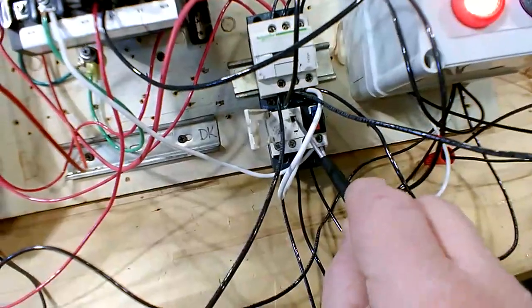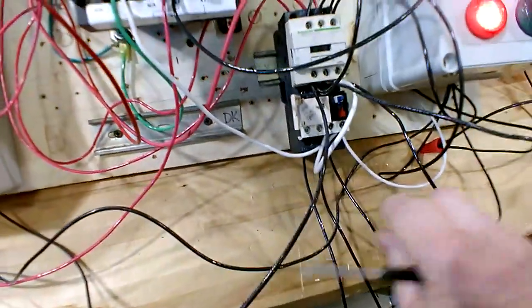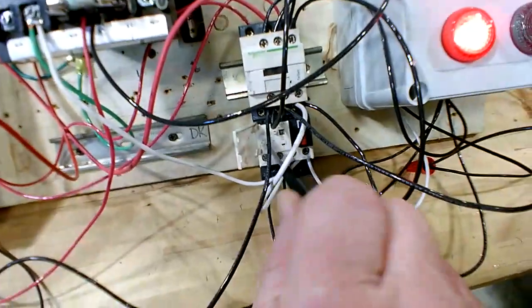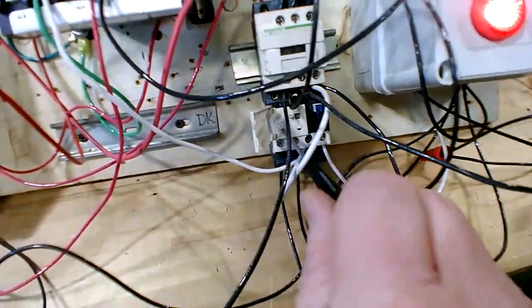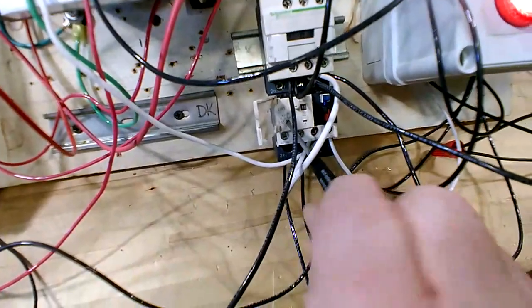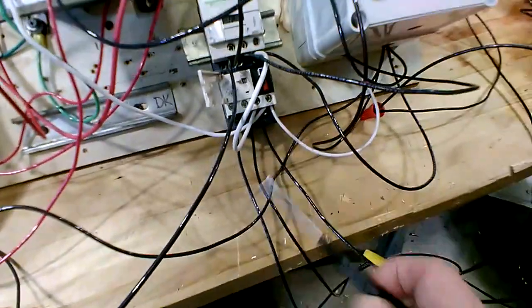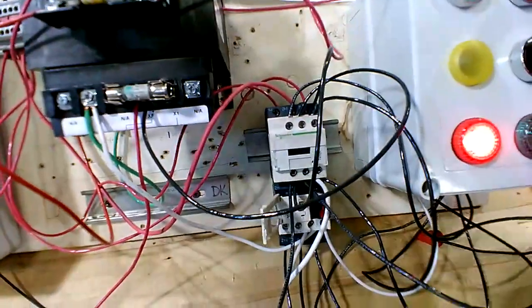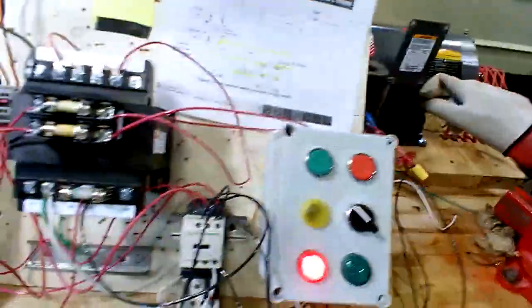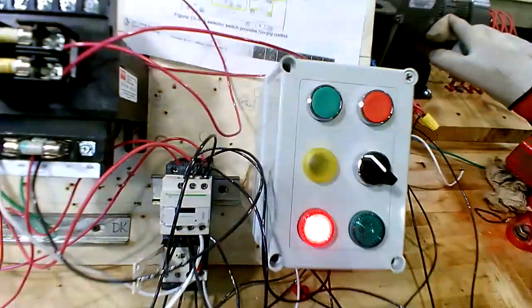Now, as far as when this thing is tripped, by the way, the amp setting in there tells you where it's going to trip at. That's when you set the job. You set that at 25% above whatever the motor runs, if you want it to just constantly run.